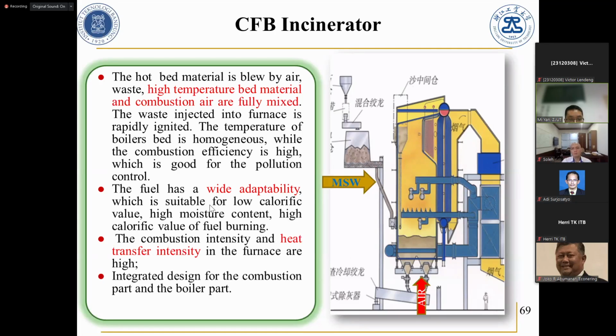The fuel has wide adaptability because the mixing is so good, we can combine coal and MSW. So the heat value change doesn't significantly influence the incineration in the CFB, and the capacity is higher. You just add some percentage of new fuel to the furnace. This is an advantage of CFB.